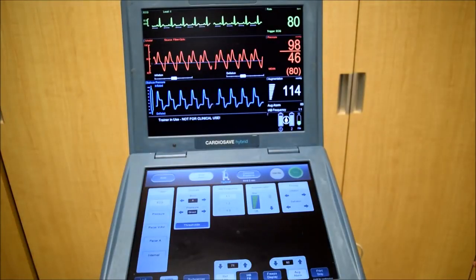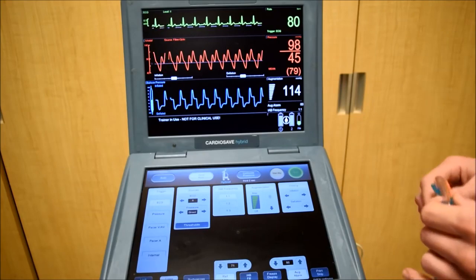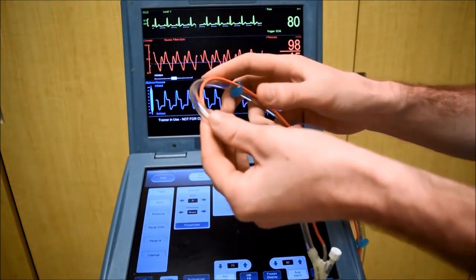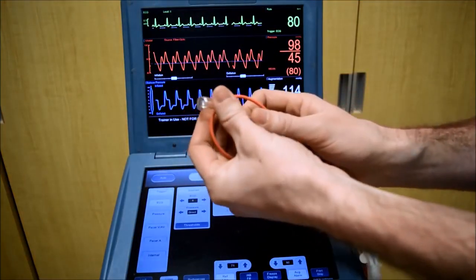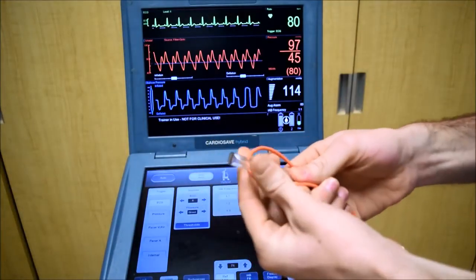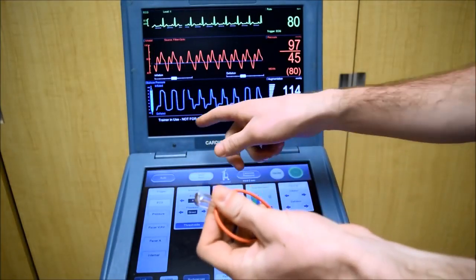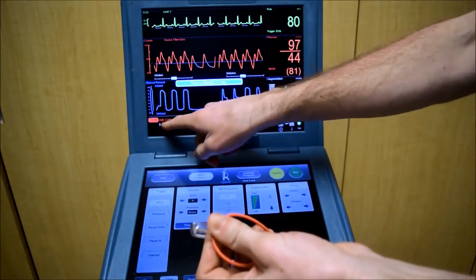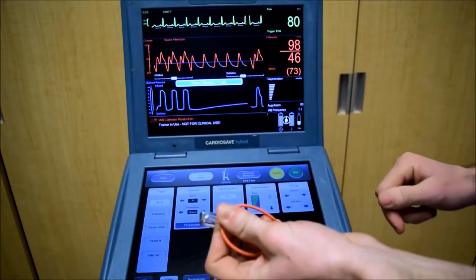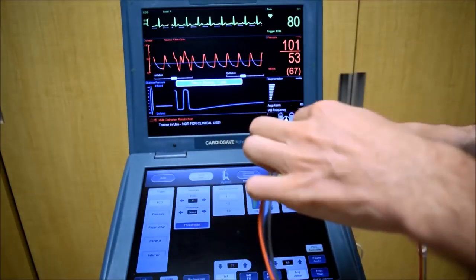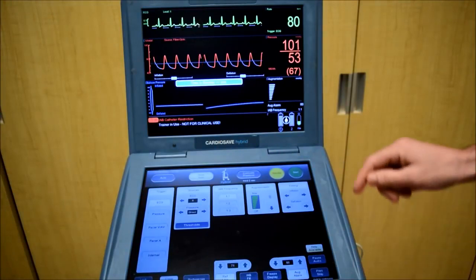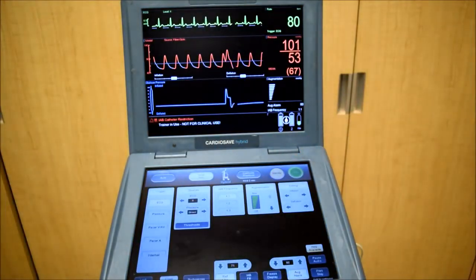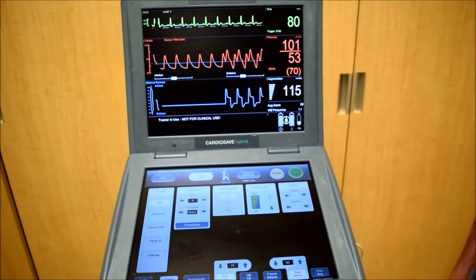I'd now like to cover some alarms you may encounter. For example, one alarm you may encounter is if the balloon catheter line is kinked. An alarm will appear. Balloon catheter restriction. Remove the kink and press start. Balloon will now resume.